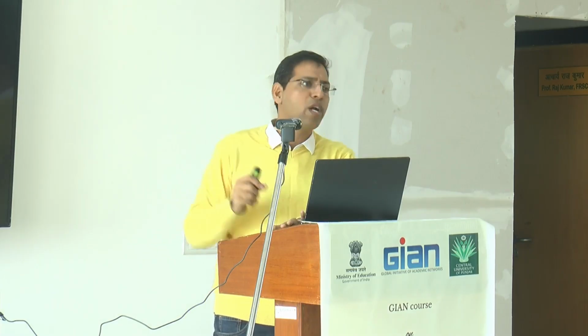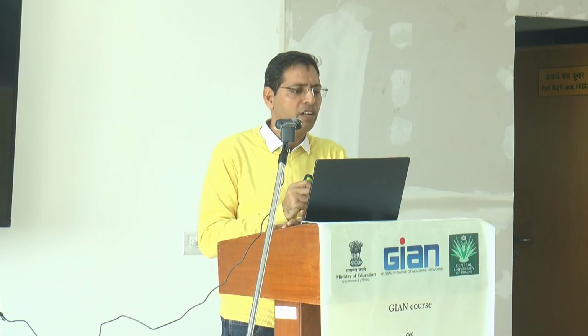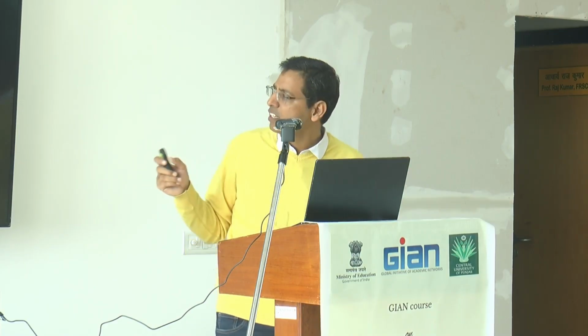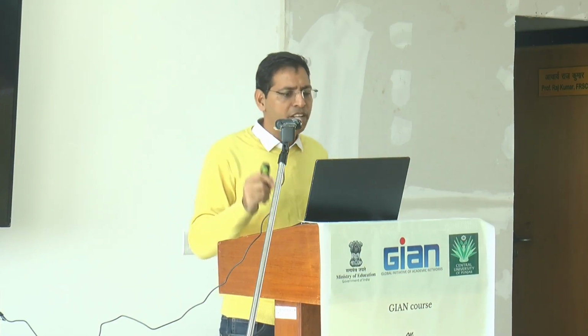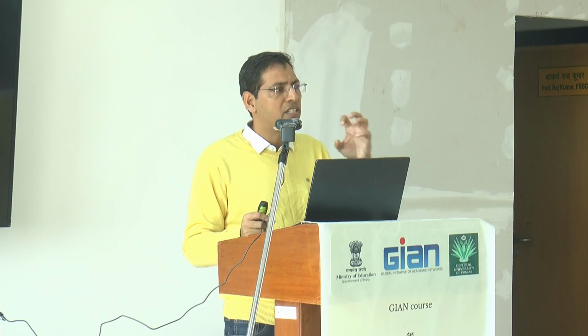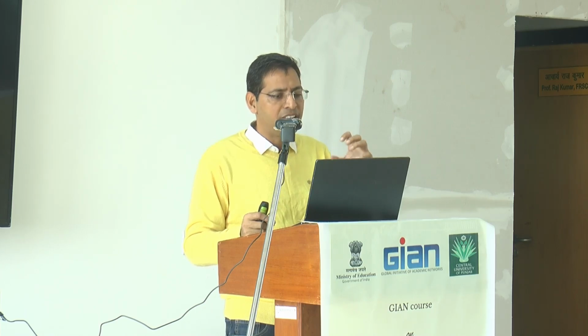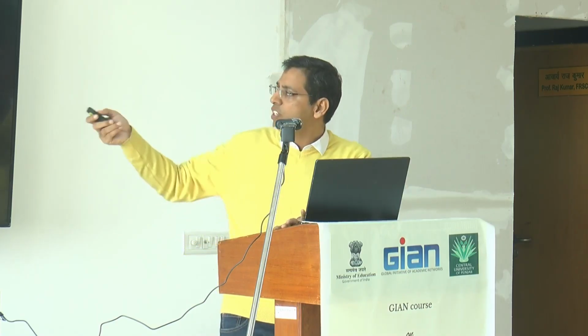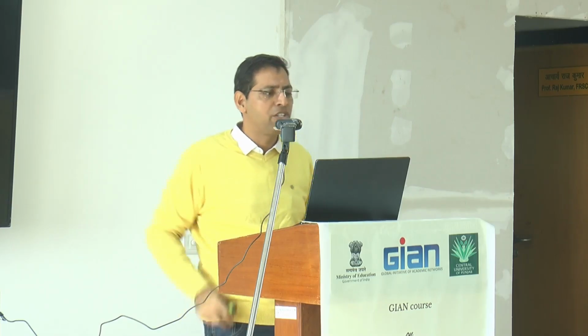Now another point comes up, that is the resolution. Resolution is an important component which resolves two peaks from each other. A resolution value of 1.5 or greater between two peaks will ensure that the sample components are baseline separated to a degree at which the area and the height of the peaks can be measured accurately. So I am explaining here: these are two peaks which are resolved very well from each other. This parameter is labeled as resolution.